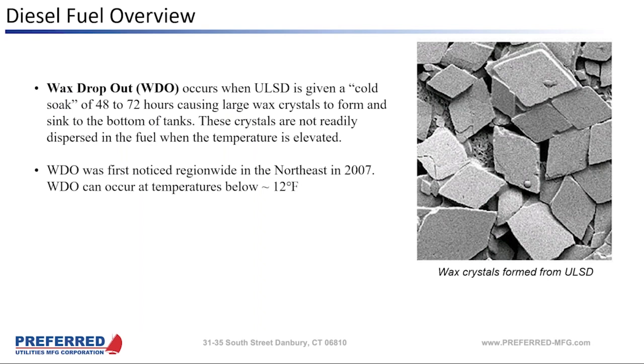Right. And then ultra low sulfur diesel has been found to have a new property called cold soak, where if the oil isn't moving and the oil is subject to cold, it forms these crystals. And I was able to find a pretty good picture of these wax crystals that form in ultra low sulfur diesel. It was first noticed in the Northeast in about 2007, and it occurs at temperatures below about 12 degrees F. So these are crystals that tend to stay crystallized even after the temperature is elevated?